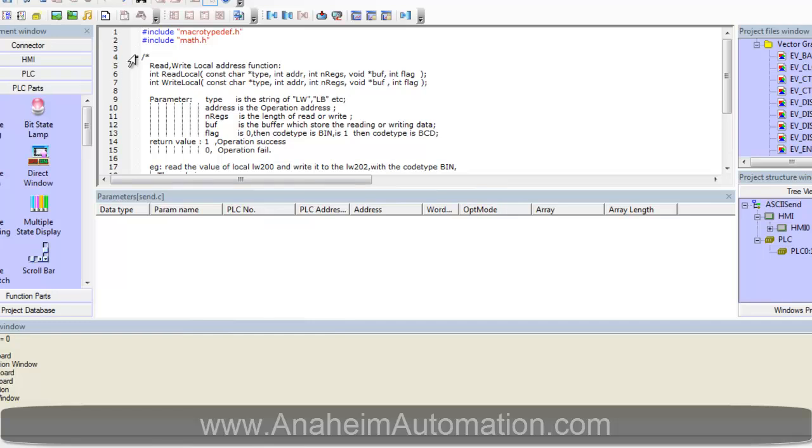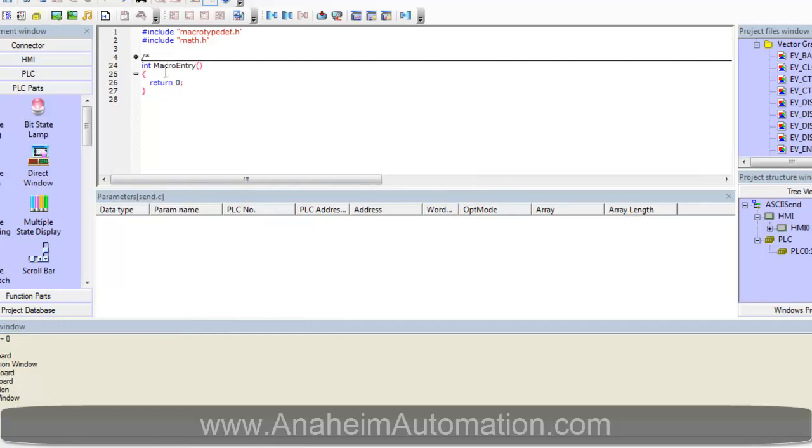We have to check both the user manual of PCL601 to get our ASCII commands that we want to utilize. And we have to also check the protocol of the universal ASCII slave that Kinco has provided us with. That protocol states that all text to be sent will be stored in register LW0 and will be sent by local bit register LB0. And in order to receive data back we must instantiate local bit 1 LB1 to be 1.